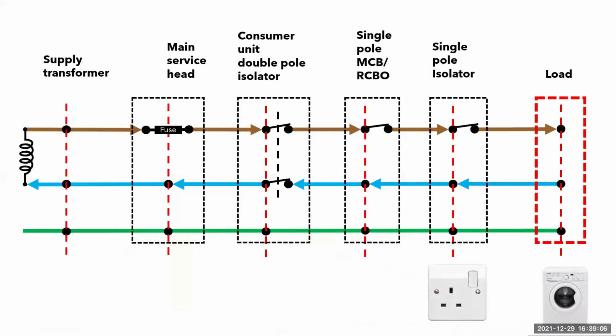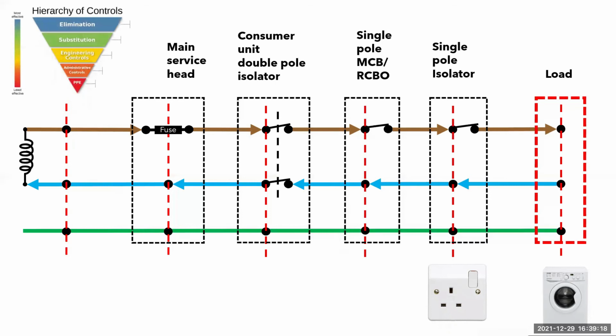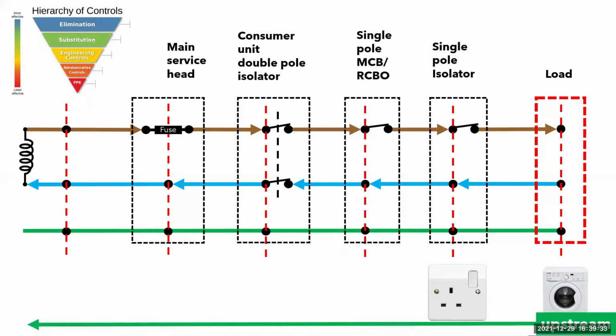Let's imagine that we want to gain access to the load. As the appliance is not working and the socket is, we want to check the electrical connections. Before we can gain access to live parts, we need to think back to the hierarchy of controls. The most effective method to protect us from a hazard is elimination. The hazard in this instance is electricity, and we can remove that hazard by isolating the supply to the appliance. We need to look upstream to isolate the supply, which means we are looking at the single pole isolator, in this instance, the single socket.